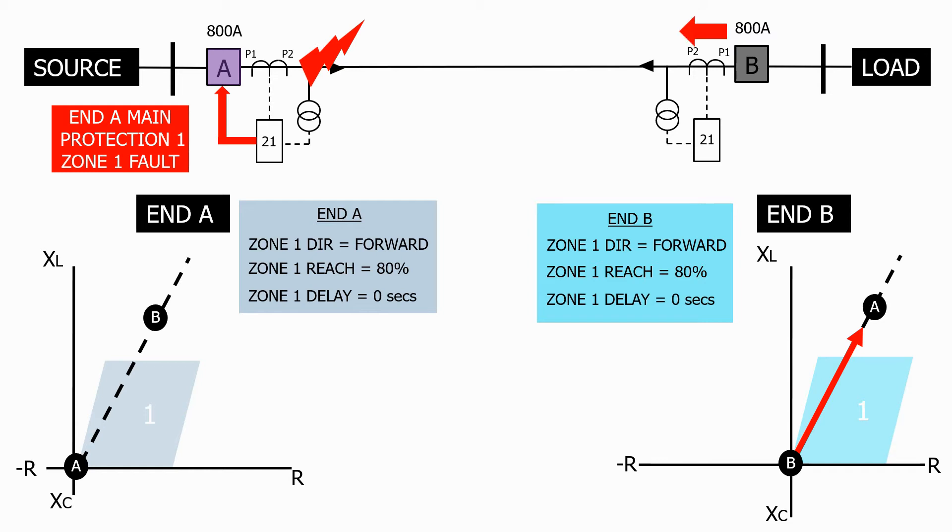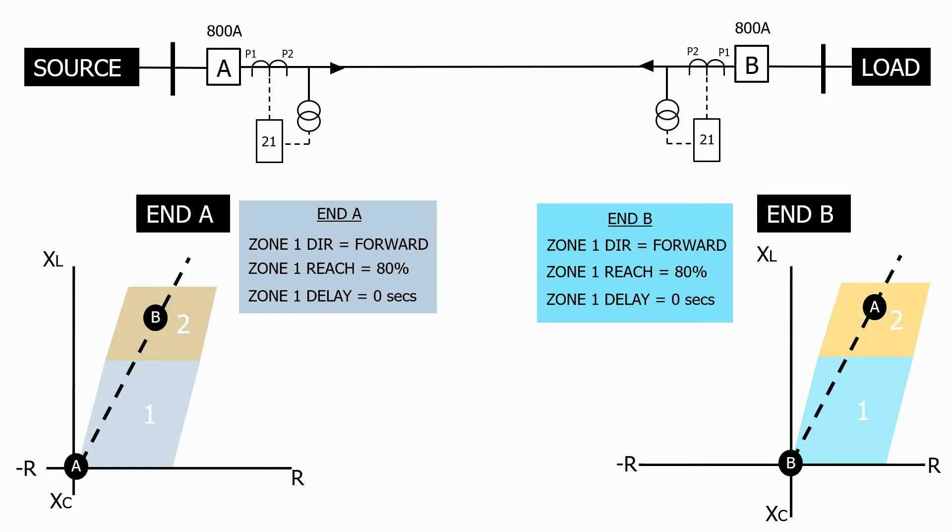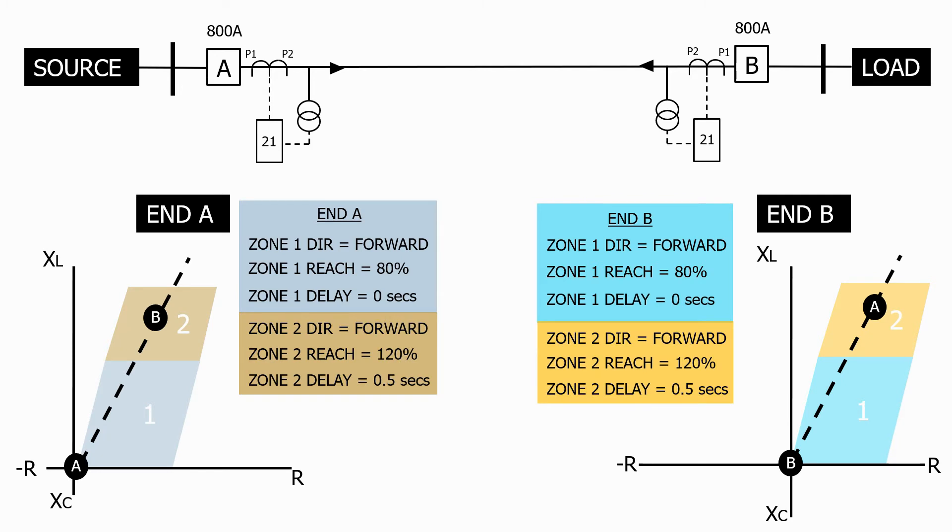To solve the problem, let's add an additional zone 2 characteristic on the impedance relays at both ends of the feeder. What will the characteristics be? Well, they both need to look in the forward direction. Let's make the reach 120% of the feeder length, and as we're not totally confident where the fault might be, let's give it a small time delay of 0.5 seconds.